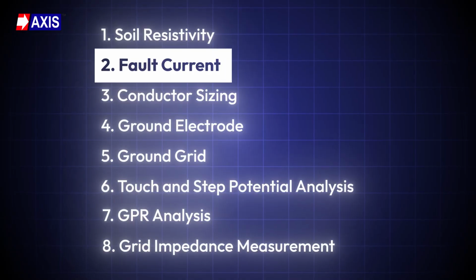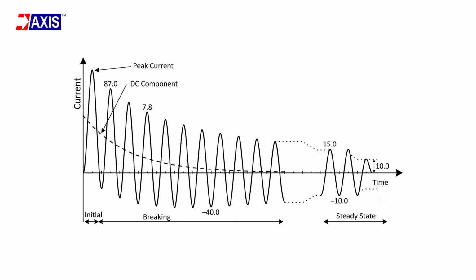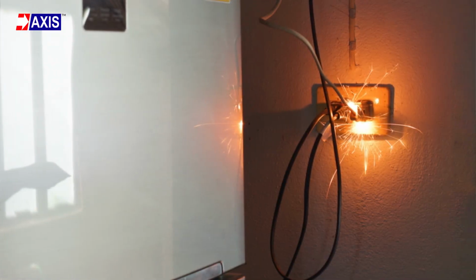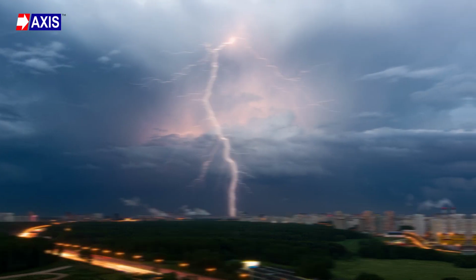Next, let's measure the fault current. With the soil model in place, the next input the design needs is fault current. This is the abnormally high current that flows through the substation during a fault condition, such as a short circuit or a lightning strike. It is not a value you design for today, it is the maximum fault current expected over the entire lifetime of your substation, including any future expansions.